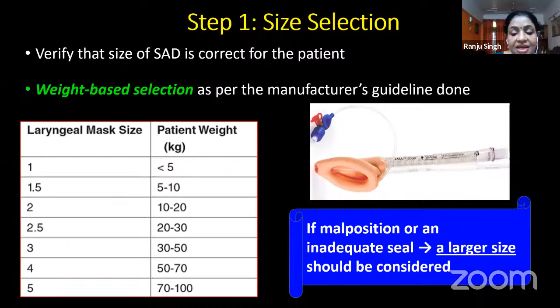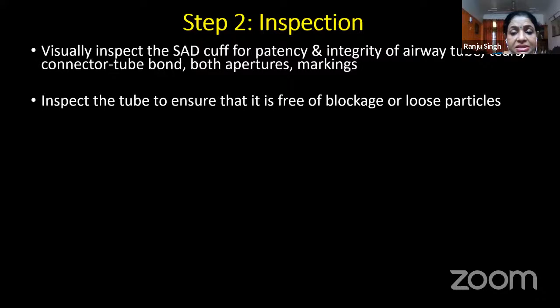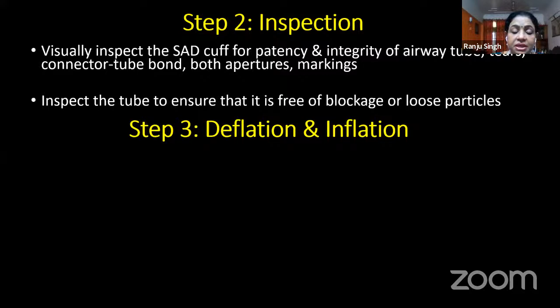The next step after you have selected the device is the inspection of the device. Always, most of these devices, even if they are single use, must be opened from the packet and inspected. Inspected for patency and integrity of the airway tube, inspect for the connector tube bond, check the apertures, check the markings on the device. Inspect the tube in reused devices to see that it's free of any blockages or loose particles, dust, or secretions within the airway tube. After you have selected the device, inspected it well, you must prepare the device for insertion. To prepare the device for insertion, the steps include deflation of the device to ensure that it maintains a vacuum.